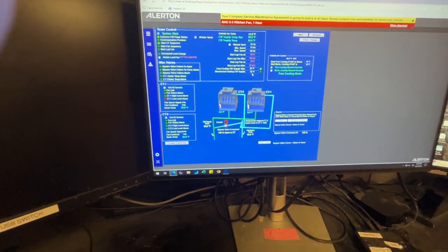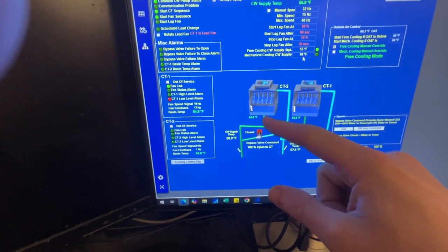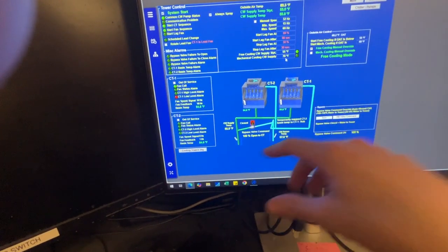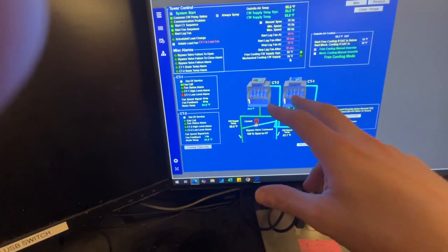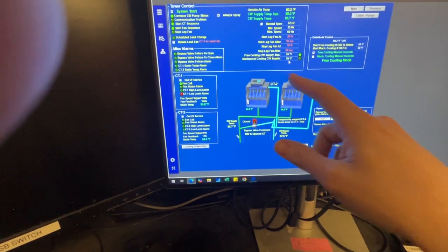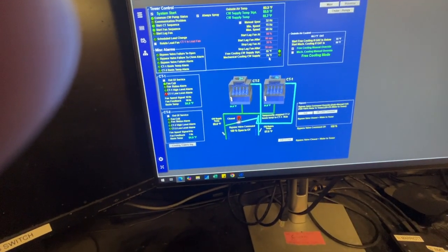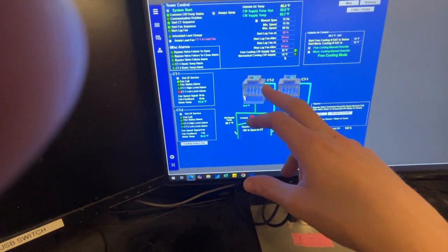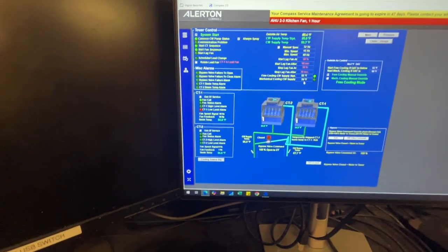The cooling towers, I would really like to see us getting actuated valves here and having Climatech rebuild this whole system. Right now you've got to climb up and change one tower to the other. Both towers are dumping water, but only one tower has the fan on. And we basically just alternate, but think of all the water that we're losing through evaporation. So, future project: putting actuating valves on the supply and return for the cooling towers.